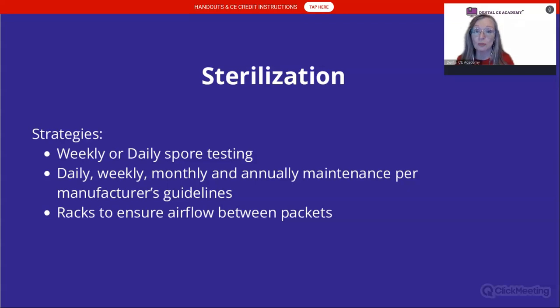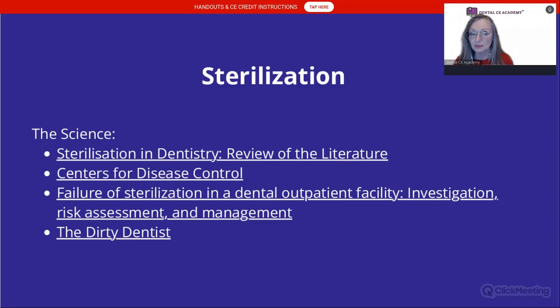Strategies here: make sure that you're spore testing your autoclaves at least weekly. That's a CDC recommendation, if not daily. If you are processing quite a few instruments, here at the county we processed 3,000 a day, so I implemented daily spore testing. The CDC does not specify the number of instruments, so you have to use your own judgment, but at least weekly. Daily, weekly, monthly, and annual maintenance is required of your autoclaves. So I recommend sending them in once a year for a tune-up. Have them calibrated, have them look at the gaskets, and so forth. And make sure that you are using the racks to ensure airflow between your packets.